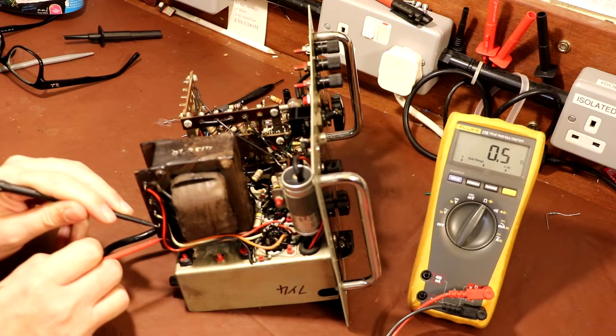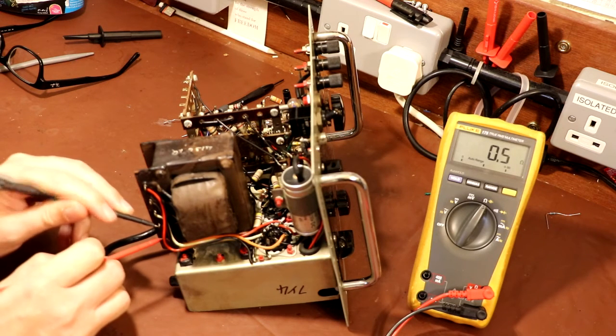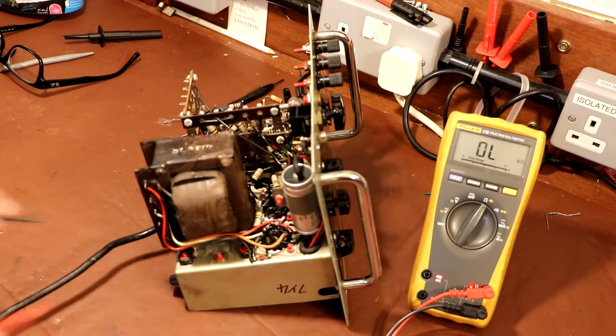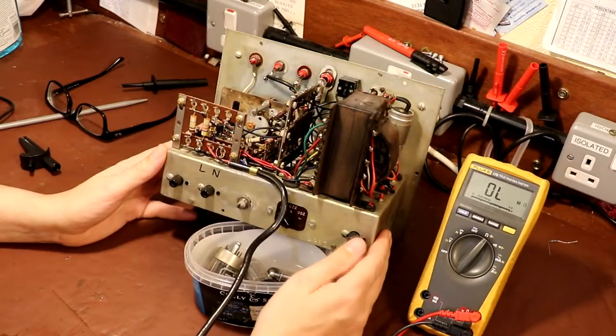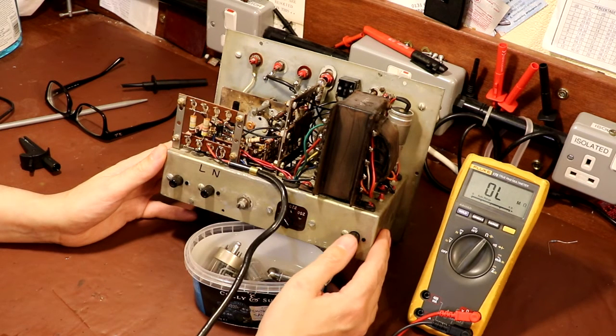Okay, we're getting a reading of 0.5 ohms there, so again we're in the ballpark, that's typical. Based on those resistance measurements, I think I have some confidence that the mains transformer looks okay at this stage. We've got no windings that are open circuit, so I'd like to go ahead and put some power onto this thing now.